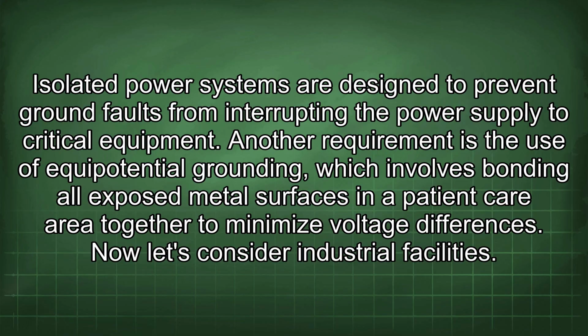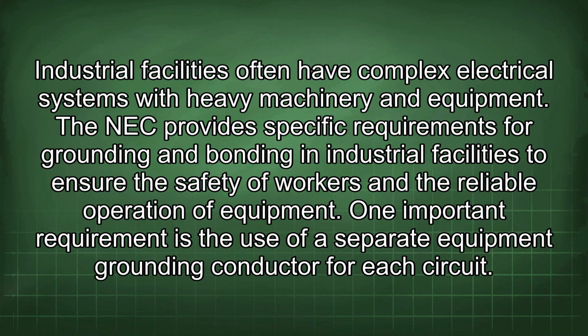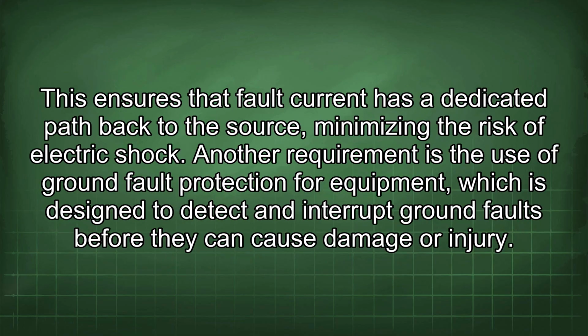Now let's consider industrial facilities. Industrial facilities often have complex electrical systems with heavy machinery and equipment. The NEC provides specific requirements for grounding and bonding in industrial facilities to ensure the safety of workers and the reliable operation of equipment. One important requirement is the use of a separate equipment grounding conductor for each circuit. This ensures that fault current has a dedicated path back to the source, minimizing the risk of electric shock. Another requirement is the use of ground fault protection for equipment, which is designed to detect and interrupt ground faults before they can cause damage or injury.